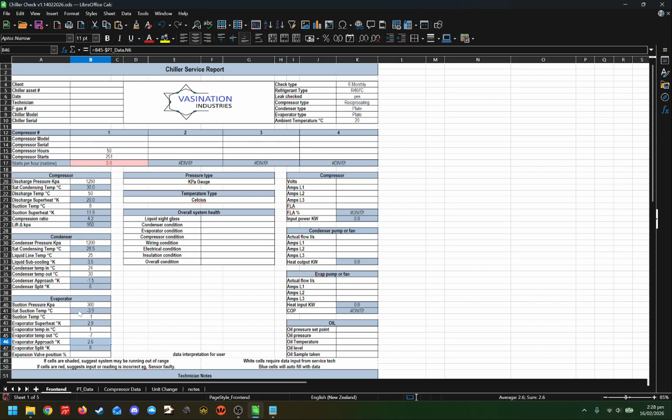Now, we have a suction temperature of, we'll call it -4 degrees, and an evaporator leaving temperature of -7. So that is just showing that we've got the glide built in. I'm saying that's not flagging it. If I said 0 degrees, we've actually got a really high approach. We've got a lot of fouling in that evaporator. And that's because it's taking into account the glide.